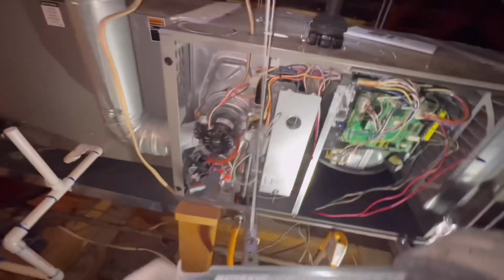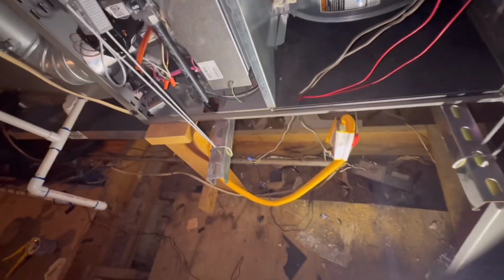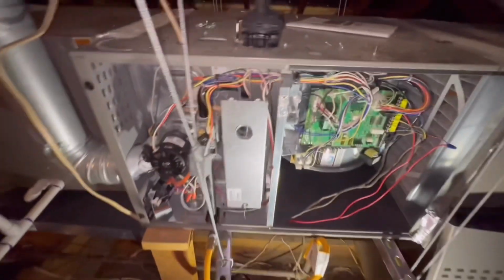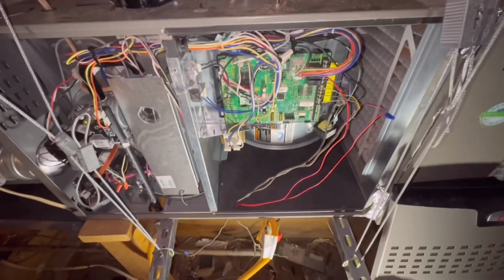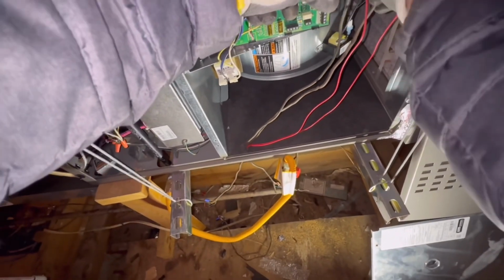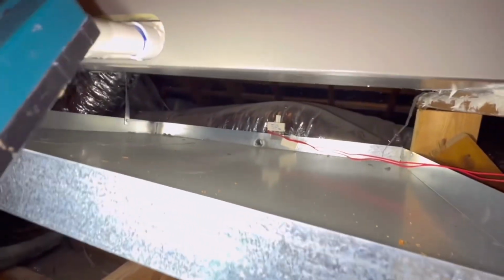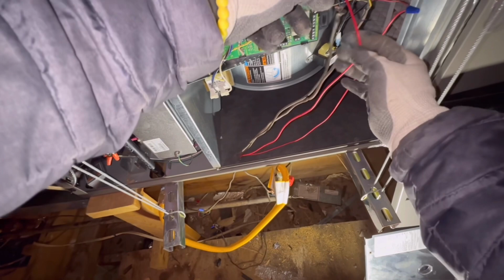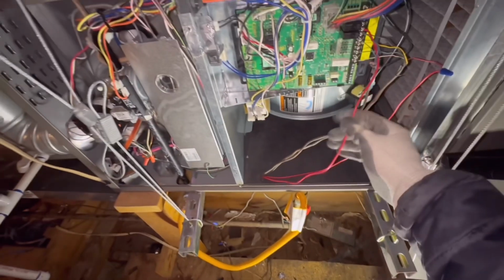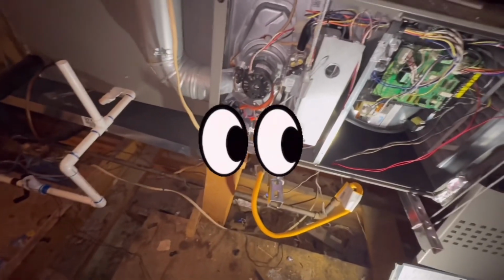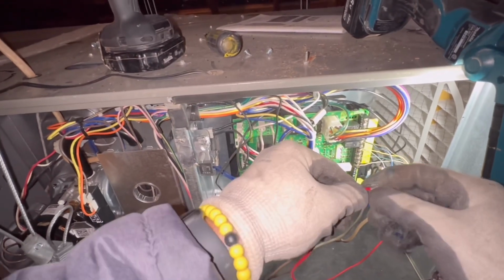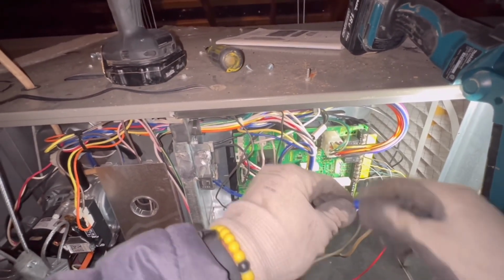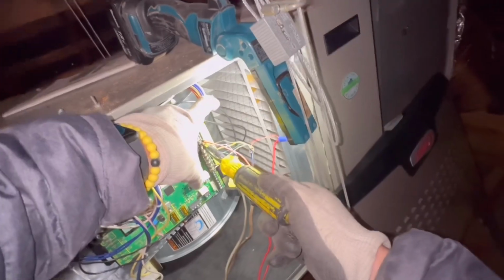Once you get into the electrical section, there is a variety of ways to wire up float switches. In this particular model here, the system already had a float switch in its emergency drain pan. That's where these 2 red wires come from that I'm holding. The best and easiest way to do this is look at the circuit board and find the letter R. Remove the wire that's connected to R and wire nut 1 wire from your float switch to the wire that was connected to the R terminal.